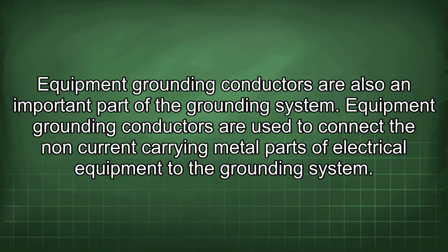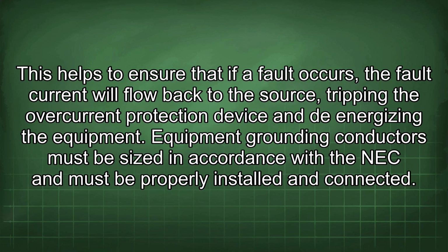Equipment grounding conductors are also an important part of the grounding system. Equipment grounding conductors are used to connect the non-current carrying metal parts of electrical equipment to the grounding system. This helps to ensure that if a fault occurs, the fault current will flow back to the source, tripping the overcurrent protection device and de-energizing the equipment. Equipment grounding conductors must be sized in accordance with the NEC and must be properly installed and connected.